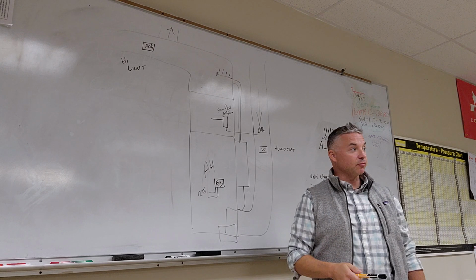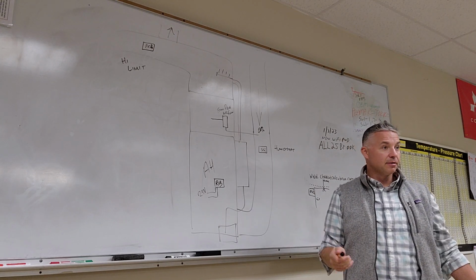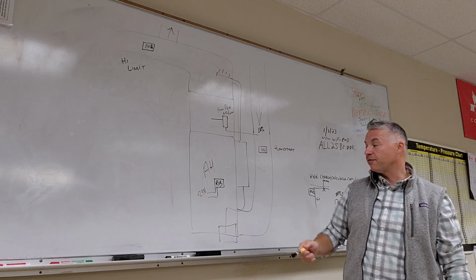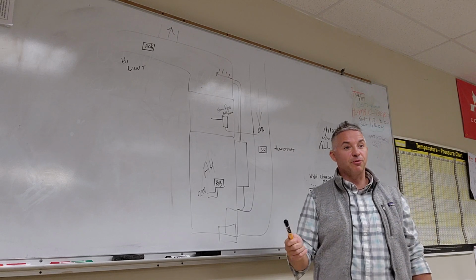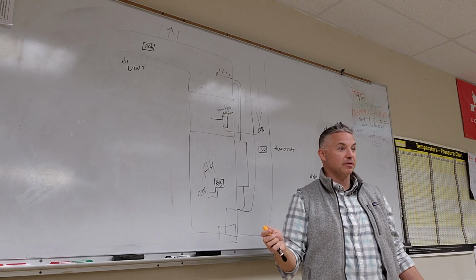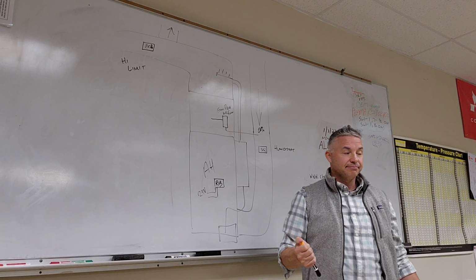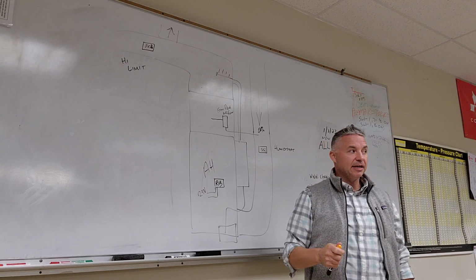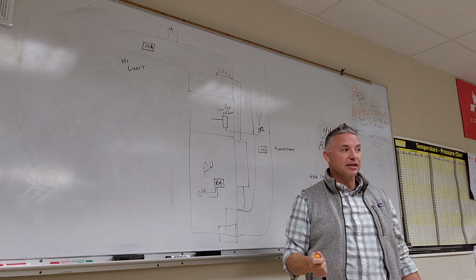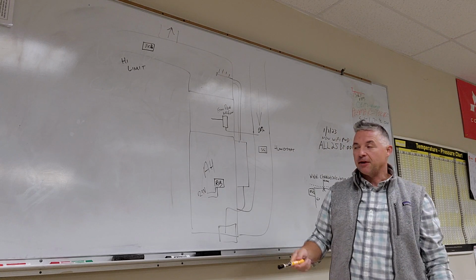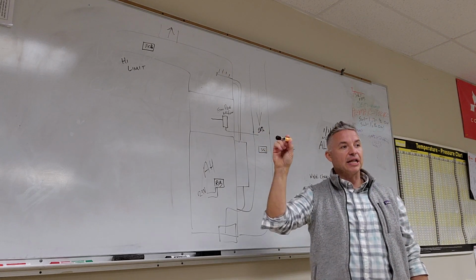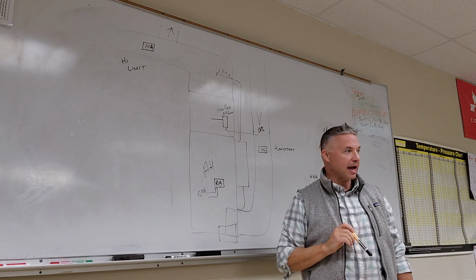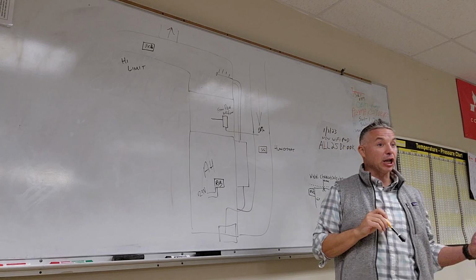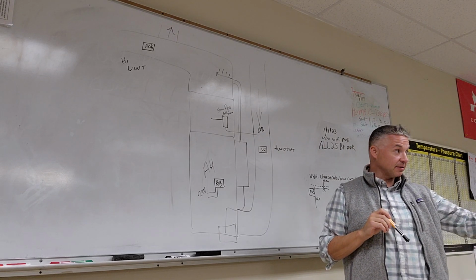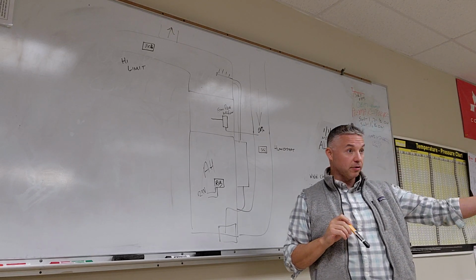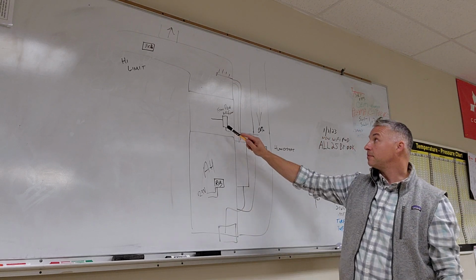And with a current sensing relay, humor me here, is it possible to send 24 volts to that fan motor, and is it possible for a current sensing relay to sense current? Yeah, I mean, they're finicky sometimes. It's dicey, it's an electronic thing, and they're finicky. If you actually have something in the ductwork telling you that, yes, I feel air, that's better than an electronic switch sensing an electric amp draw through a wire, right?